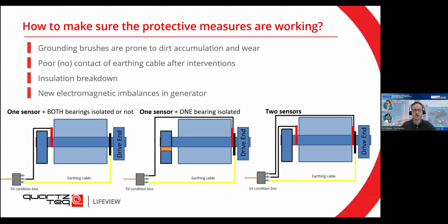And maybe your current setup of the shaft grounding is not enough to essentially divert all this new shaft voltage and current. So our suggestion here is to use additionally a sensor that tells you what is the shaft voltage. And also you can measure some current going through the earthing cable. Once you establish this, you can monitor if the voltage grows or it stays the same, and it gives you an indication of both the health of your machine, and second, also the health or the performance of these countermeasures I showed you in the previous slide.